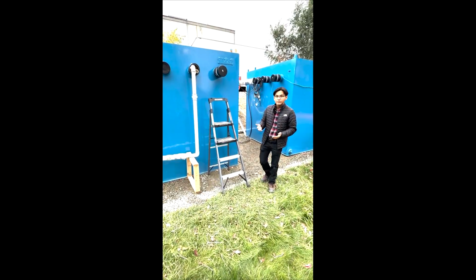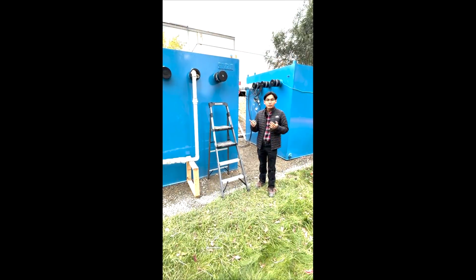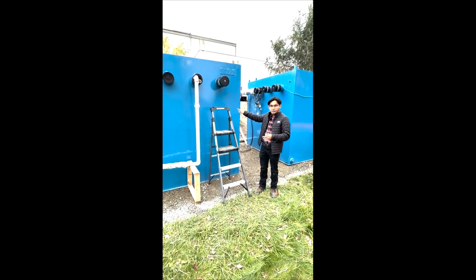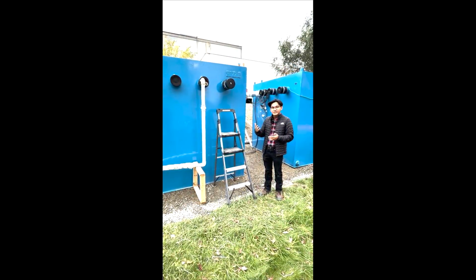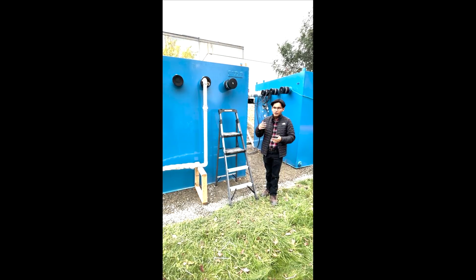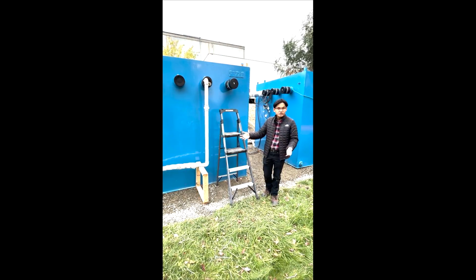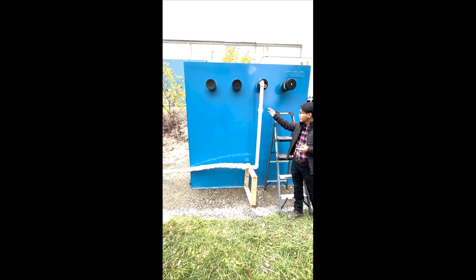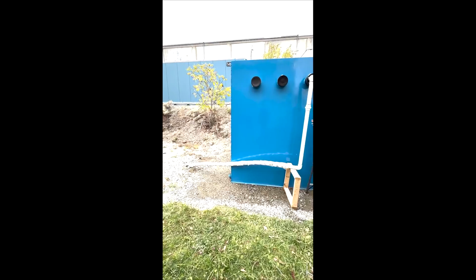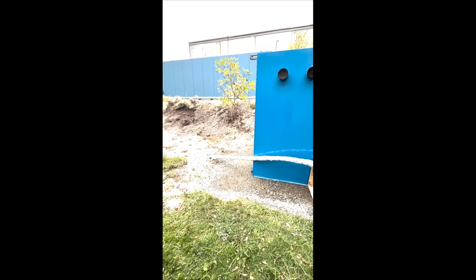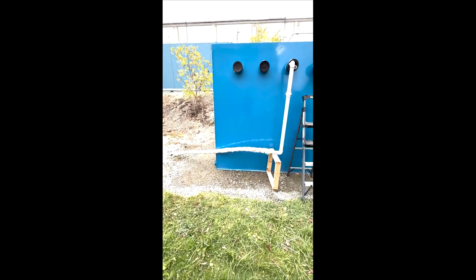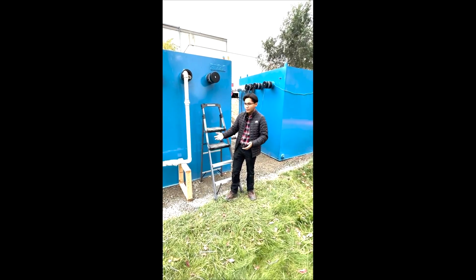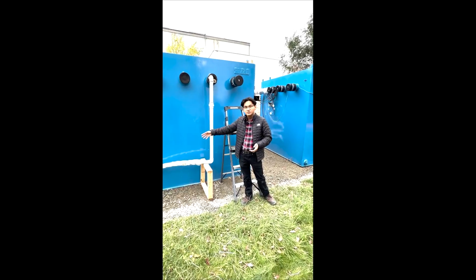Okay, so you may be wondering what happens to all of the water and all the waste that we're generating on site. The first thing we're doing is we are ensuring that no contaminants, no sludge, nothing is going into the lake. And how do we achieve that? By sending any undesirable compounds first to this tank. This tank is leading to the sanitary sewer, and it contains anything that might harm the environment. So sludge or any water that has high concentration of chemicals gets sent to sanitary sewer where it can be treated.